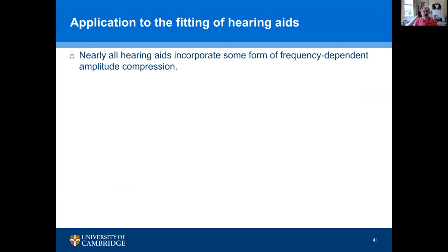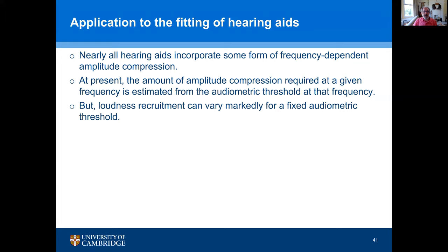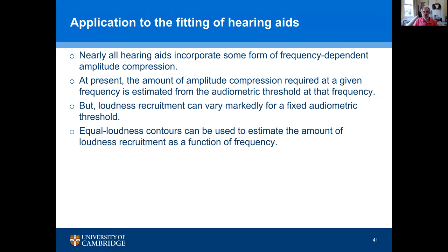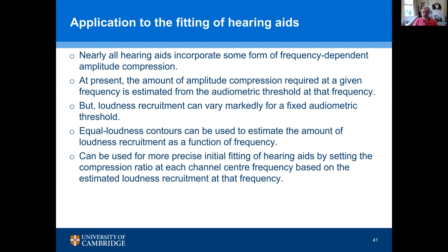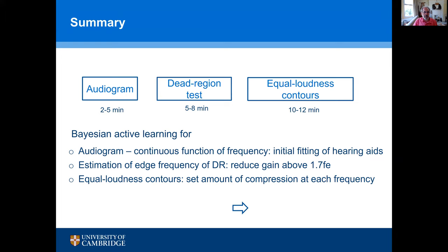This could be applied to hearing aids when adjusting compression. Nearly all hearing aids incorporate frequency-dependent amplitude compression, but currently the compression required at a given frequency is estimated from the audiometric threshold at that frequency — which is not really adequate because loudness recruitment can vary markedly for a fixed audiometric threshold. We think equal loudness contours can be used to estimate the amount of loudness recruitment as a function of frequency and to set the compression ratio at each channel frequency based on the estimated loudness recruitment using the equal loudness contours. To sum up, I've described three tests that can be performed rapidly using Bayesian active learning: the audiogram, edge frequency of a dead region, and equal loudness contours — which we think can lead to more personalized hearing aid fitting in a relatively short time.